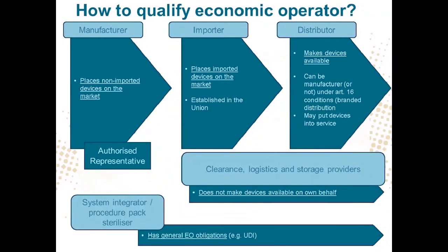Now, crucial to understand the economic operator regime is to know who is what economic operator. The systems integrator and procedure pack sterilizer that I've put on the bottom of this slide are only relevant to the general medical devices regulation, the sister regulation of the IVDR. But as an IVD company, you might get involved with this when you are making, for example, systems or procedure packs that include an IVD and that are regulated under the MDR. Then you might become a systems integrator or procedure pack sterilizer under the MDR.